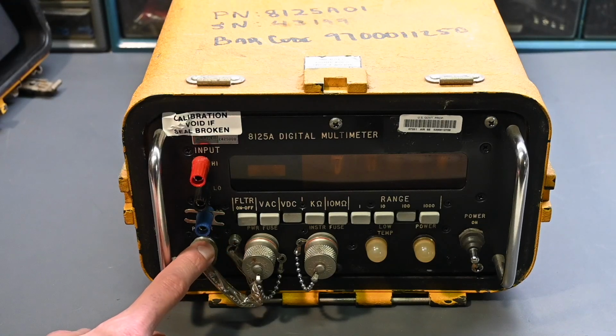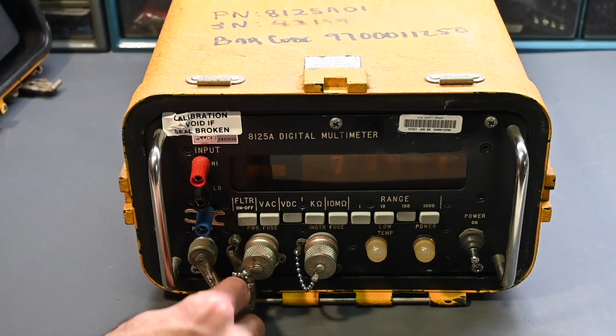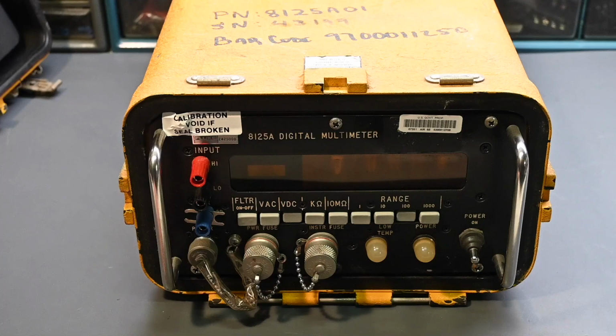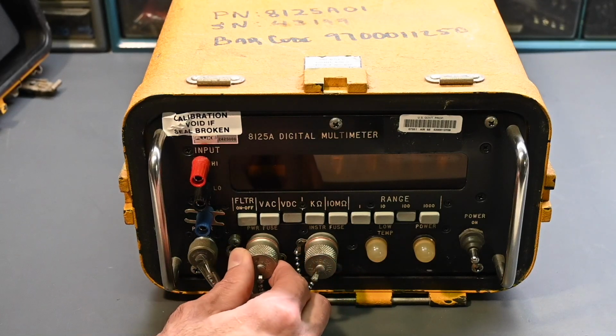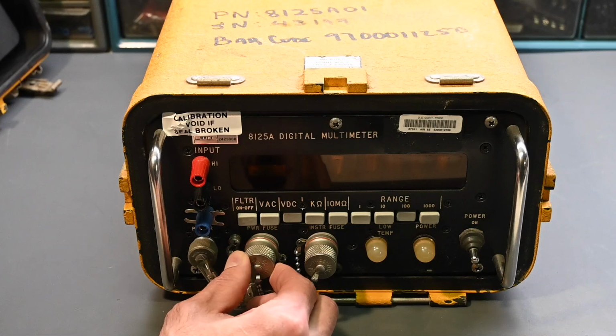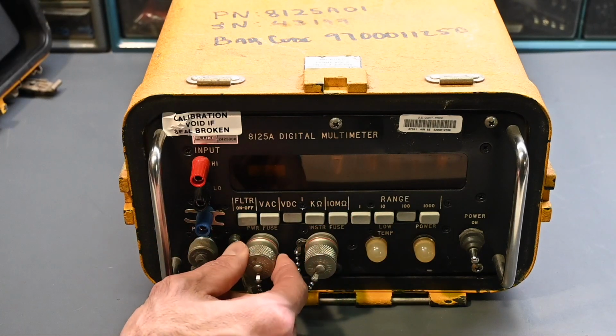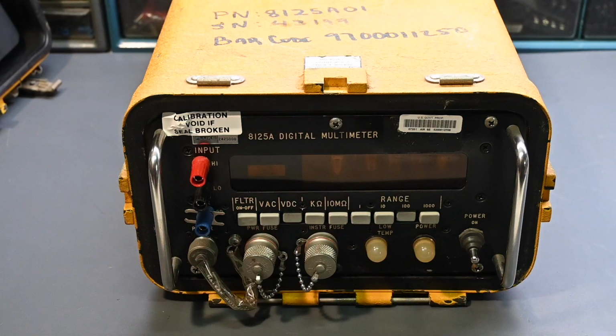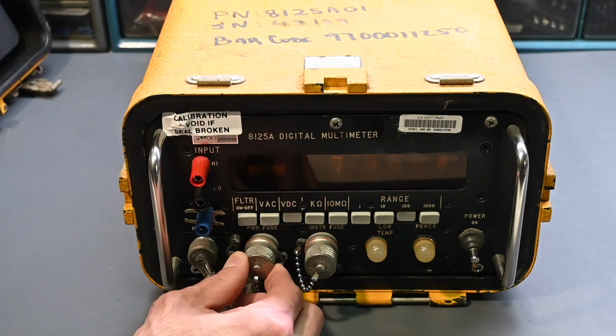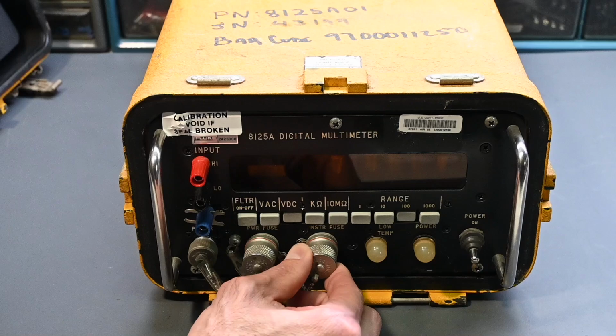There's a connector here for the AC line input with a dust cap and a little retaining chain, and 2 fuse holders, which brings me to the next issue. Both of these fuse holders are loose. There's no way I'd want to power up this instrument in this condition, because I don't know if they've been twisted around and the wiring is maybe broken off, or if the fuse holder itself is broken somehow, but you can see how loose that is. I don't like that at all.